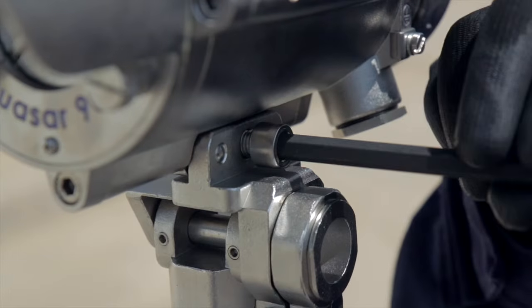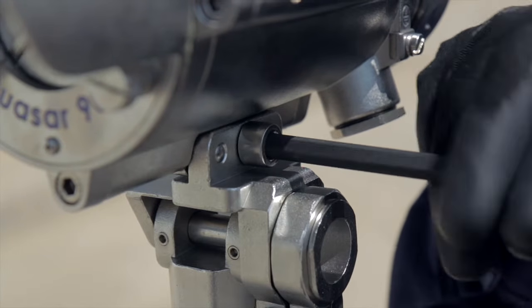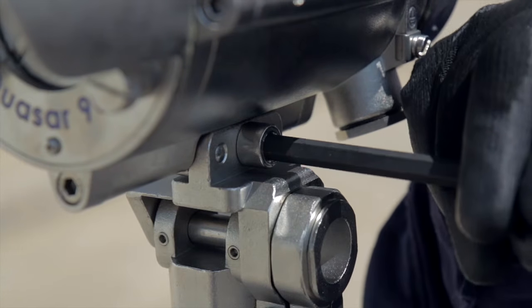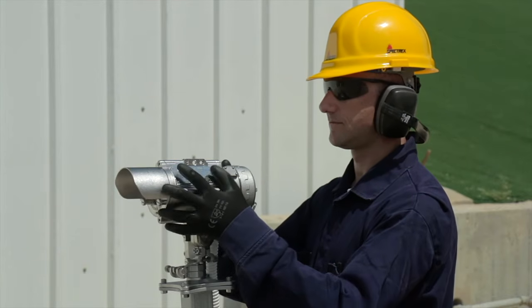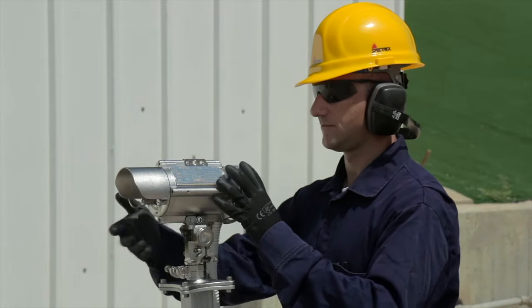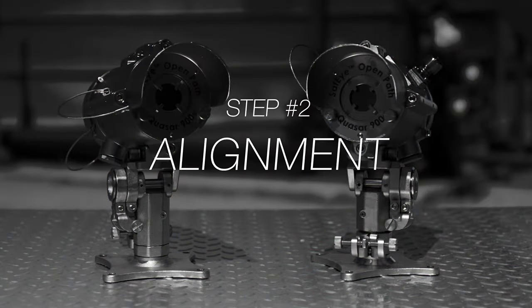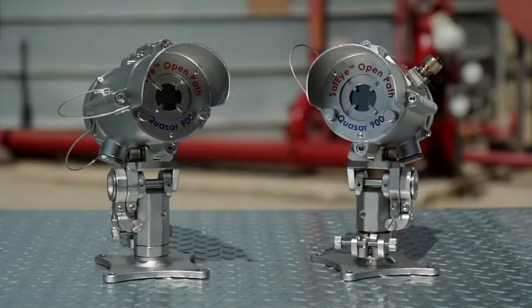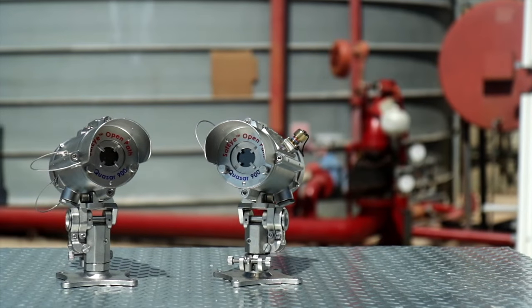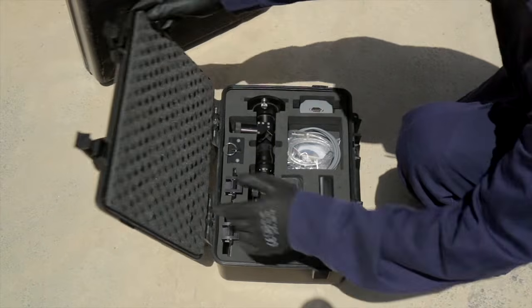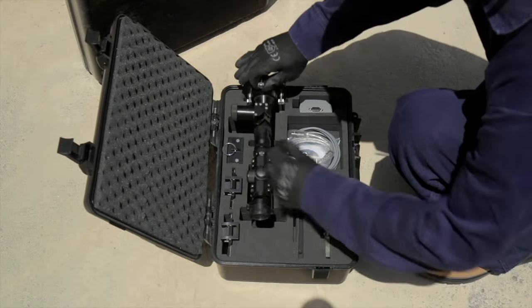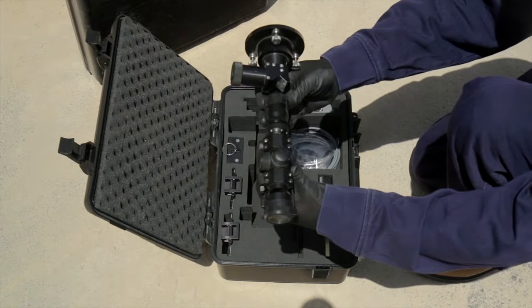Tighten the screws with the hex key. Follow the same steps for the detector as well. When done, make sure that the unit is secure and not vibrating or loose. The next step is to perform an alignment of the transmitter and receiver. The alignment process consists of 3 stages: crude, fine, and zero calibration. An alignment telescope will be used to perform a fine alignment of the source and detector.